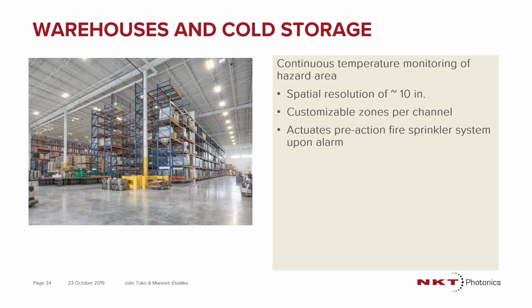Another application is warehouse and cold storage for linear detection, especially fiber optic. We see more interesting approaches from an insurance point of view. I would like to point out that you can monitor not only the cold storage, but you can also turn the system into temperature monitoring. So you can know which area is now being cooled properly. And you can also pinpoint exactly where, if an event or a fire is happening, you can literally decide what you're going to act upon, whether or not you're going to, let's say, activate some kind of deluge system or do some other form of intervention.